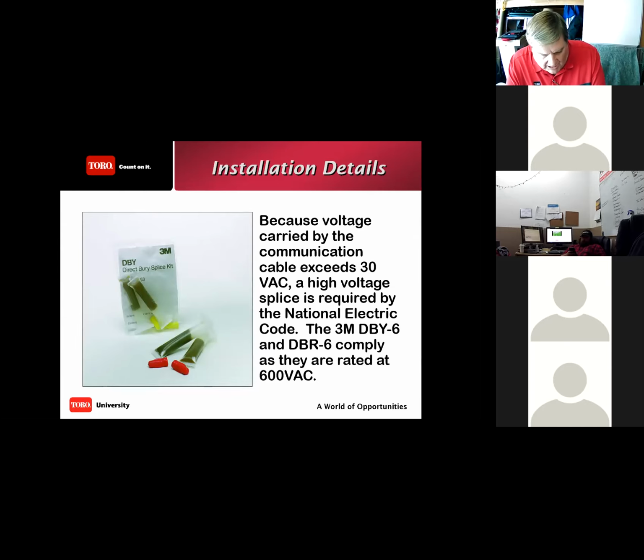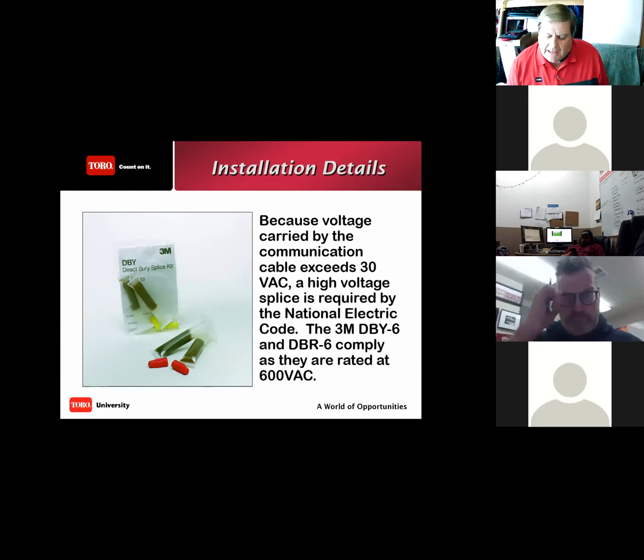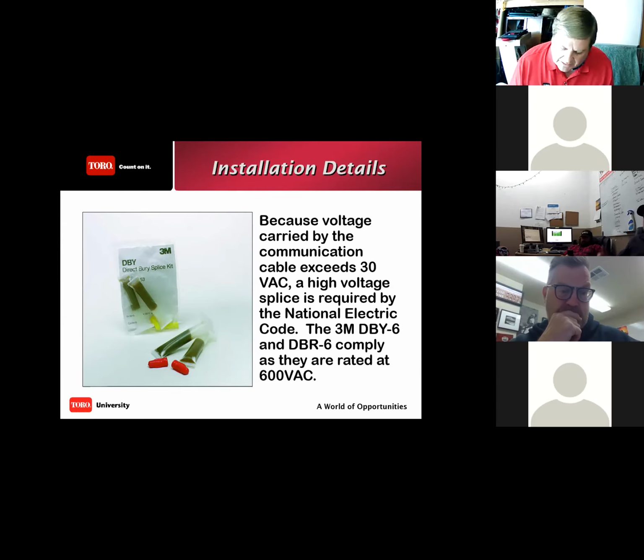Wire connections. I can't stress this enough. On 2-wire systems, 85% of all the problems that you're going to encounter out there are going to be related to a wire connection. And I will say each and every single solitary wire connection ever made will eventually have to be replaced. They don't last forever. And on 2-wire, specifically 2-wire, the wire connections are critical.